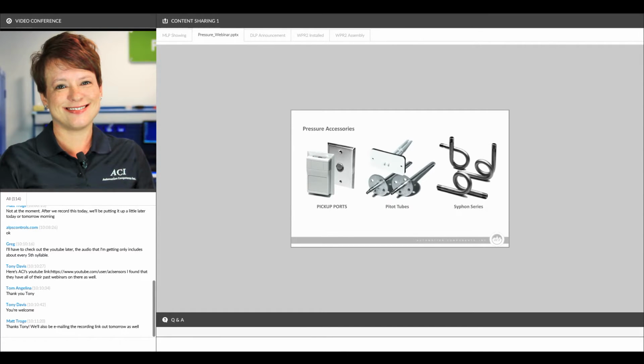ACI does make a line of accessories to go along with all of our transducers. Some of those accessories include pickup ports. We have those available in both room and outdoor air configurations. We have a line of pitot tubes in static, differential, and velocity configurations. And we also sell a line of pigtail siphons. And we strongly recommend the use of these siphons in any steam or other high temperature application where you need to bring the temperature of the media down to something safe enough for the GP or the WPR2 to read.